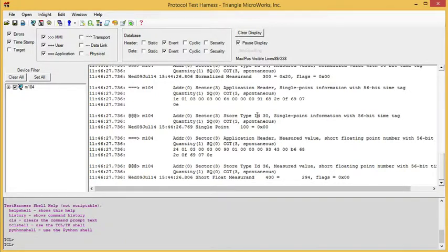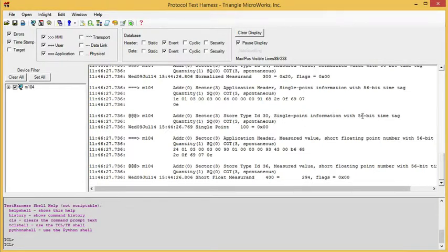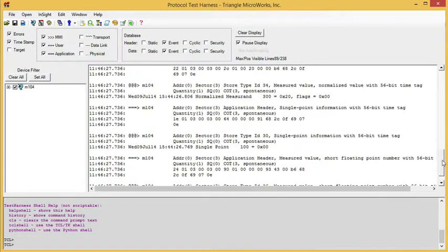And now if we pause and look for data, here we have a type ID of 30, single point information with 56-bit time tag. I have a type ID 36, measured value short float with 56-bit time tag.